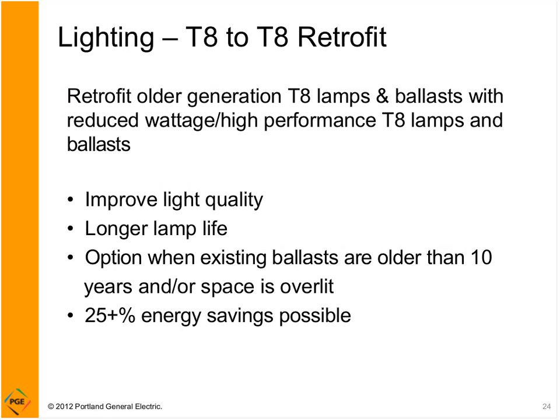As we talked about earlier, retrofitting T12s with newer generation high performance T8s. There's also potentially an opportunity to replace older generation T8 lamps and ballasts with reduced wattage, high performance T8 lamps and ballasts. So you'll see a jump in the color rendering index with this particular upgrade. Longer lamp life: standard T8 is still in the 20,000 hour range, and as I mentioned earlier, 24 to 50,000 hours with reduced wattage or high performance T8s. So this is an option when you're faced with failing ballasts. Let's say the ballasts are 10 or 15 years old.